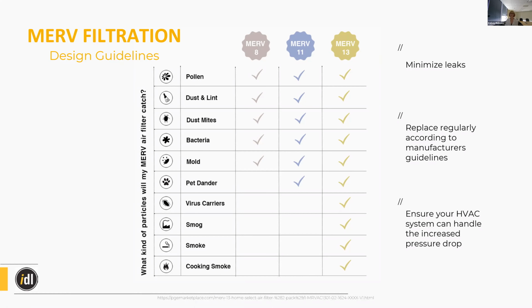But as far as other design guidelines go, right sizing your MERV filter is really important. If you get a MERV filter that's an inch too small on each side, then all the air is just going to go right around it, and the filter doesn't really do much. So you want to make sure that you buy exactly the right filter size for your air handling unit, and even ASHRAE recommends taping it or using gasketing and really sealing up those leaks to get at that 89% efficiency. The leaks are key. And also, again, just ensuring that your HVAC can accommodate the increased pressure drop or rise.